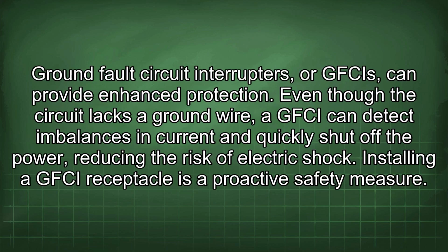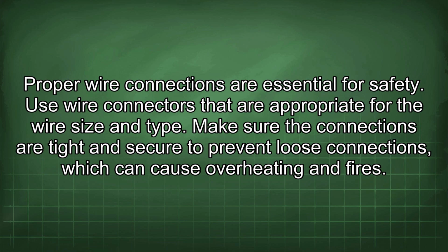Ground fault circuit interrupters, or GFCIs, can provide enhanced protection. Even though the circuit lacks a ground wire, a GFCI can detect imbalances in current and quickly shut off the power, reducing the risk of electric shock. Installing a GFCI receptacle is a proactive safety measure. Proper wire connections are essential for safety. Use wire connectors that are appropriate for the wire size and type. Make sure the connections are tight and secure to prevent loose connections, which can cause overheating and fires.